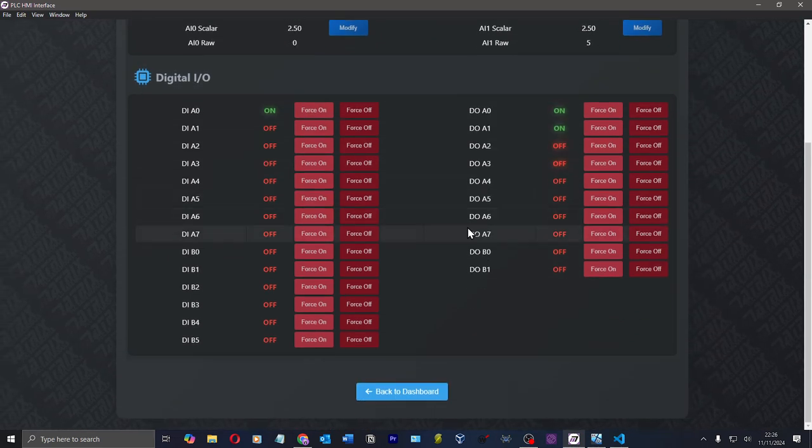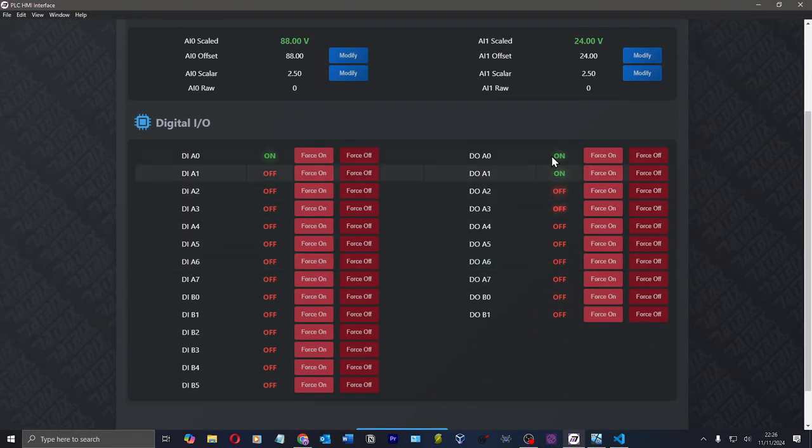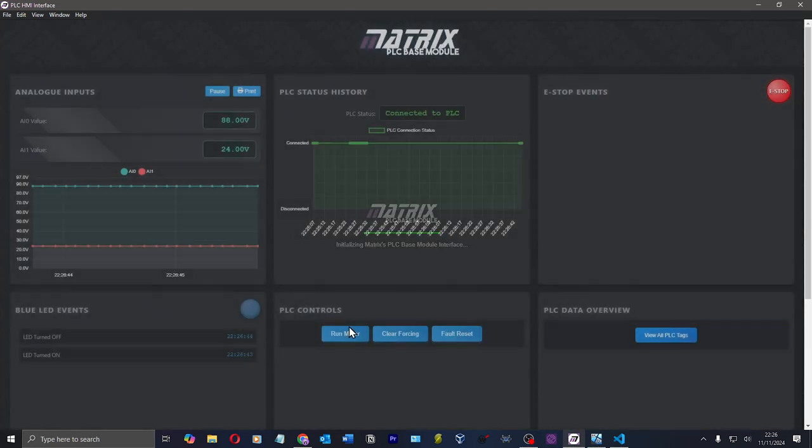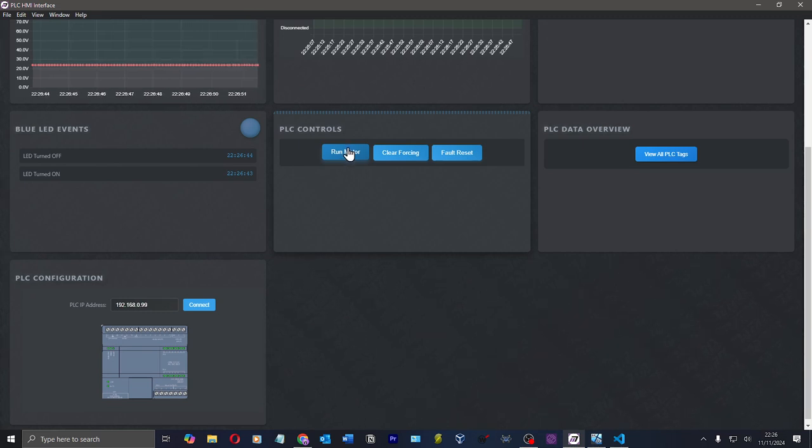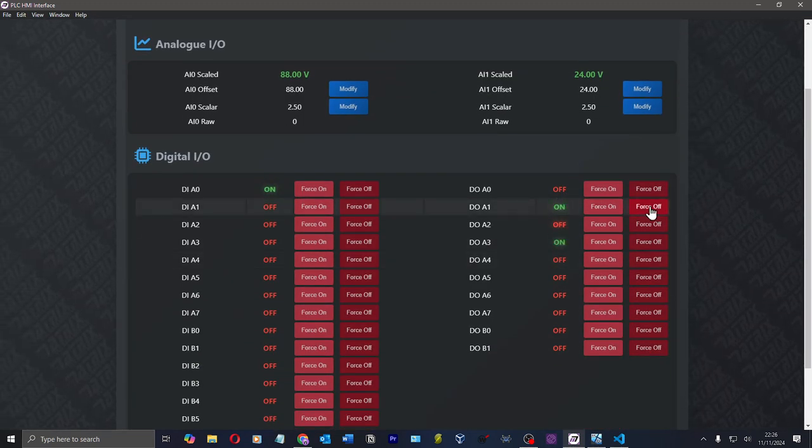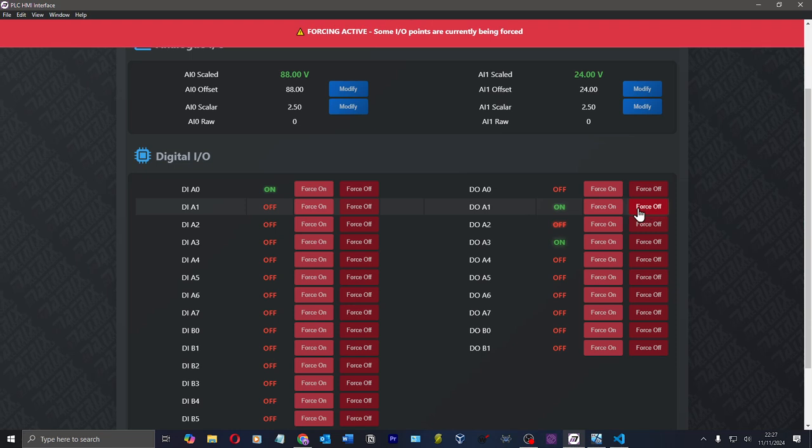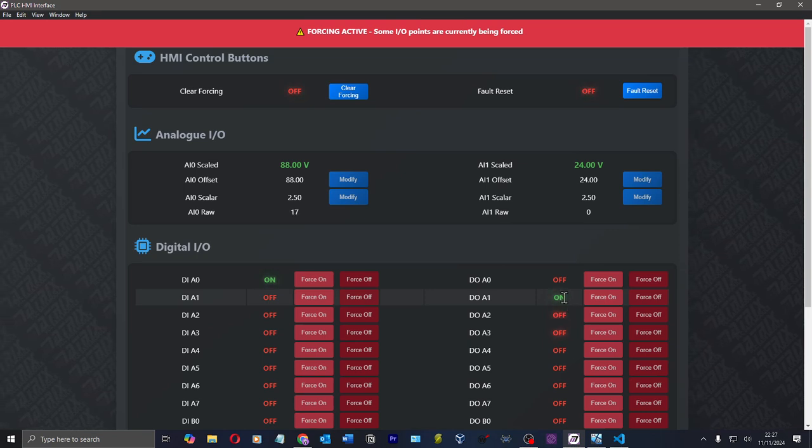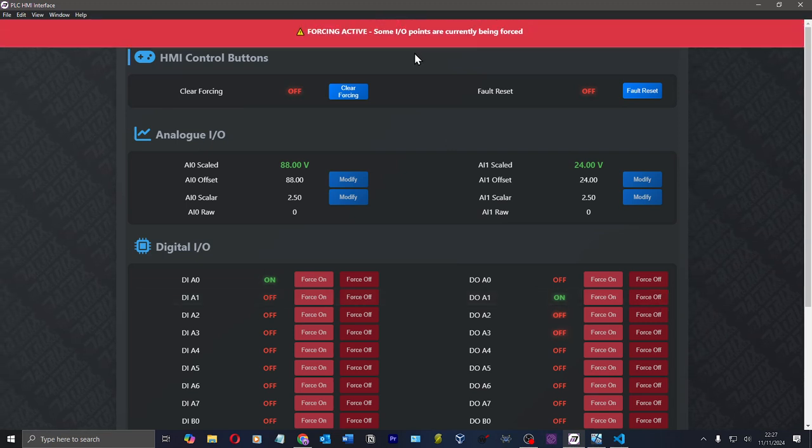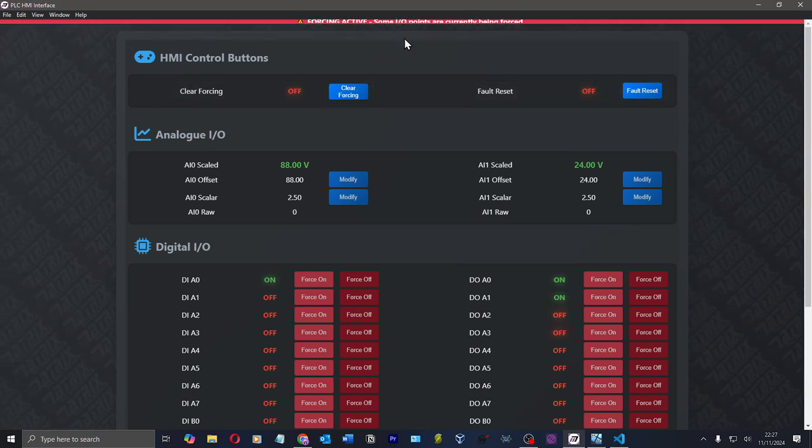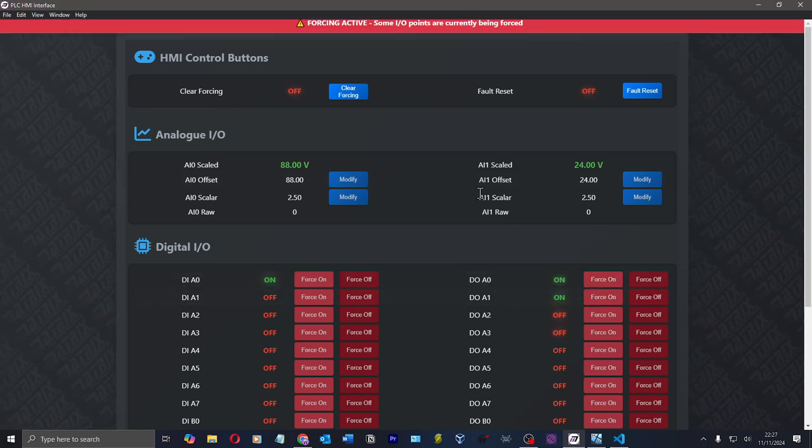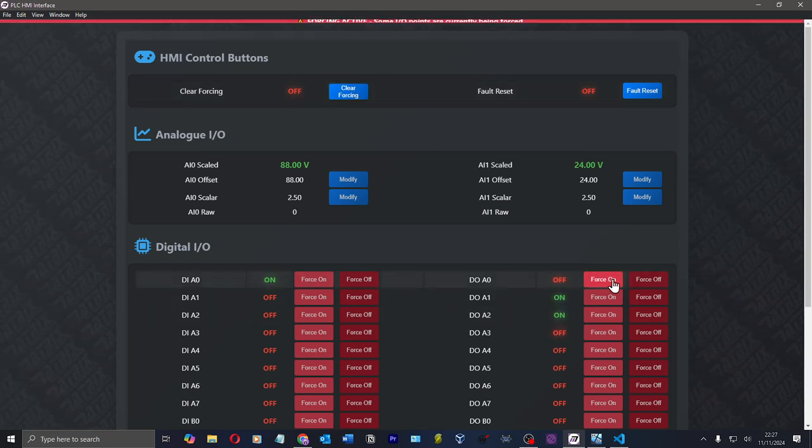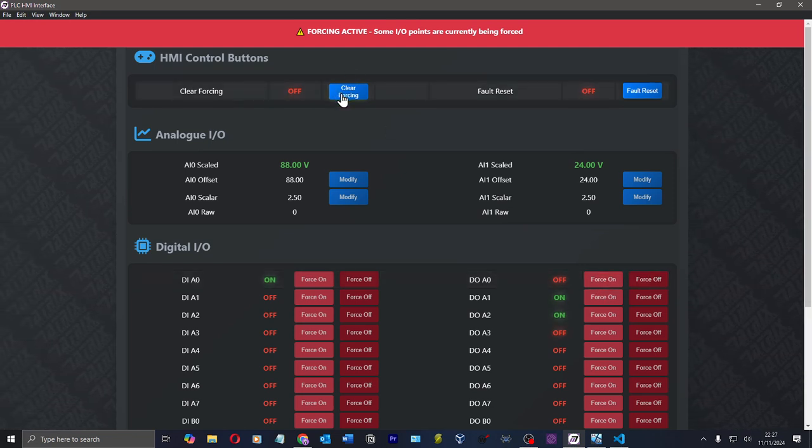And then here's the crazy part. Now, if you don't know forcing, this will blow your mind, but essentially the program right now is running. I clicked that run motor button back here. I've toggled it. So that's on. Digital output one is on. I can, the PLC is telling it to turn on. I can force it off. And so even though now in the PLC, it's turned on, I am able to force it off. And then I've got this banner that pops up and bounces. Here it says forcing active. Some IO points are currently being forced. And so if I clear forcing, that banner goes away.